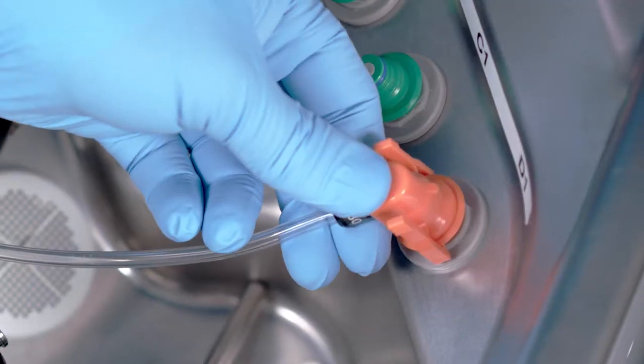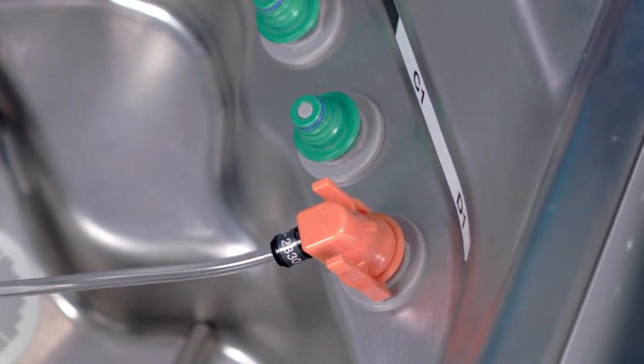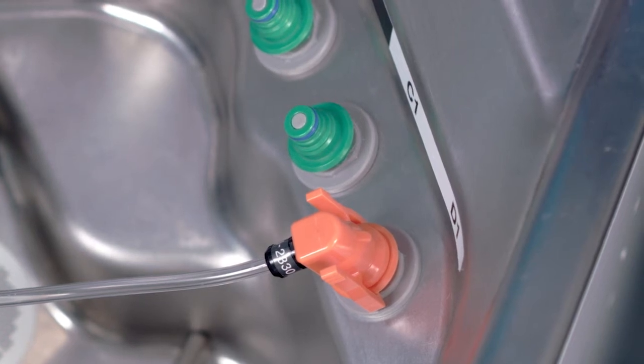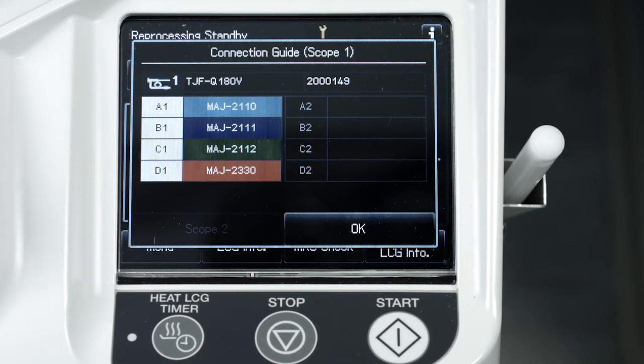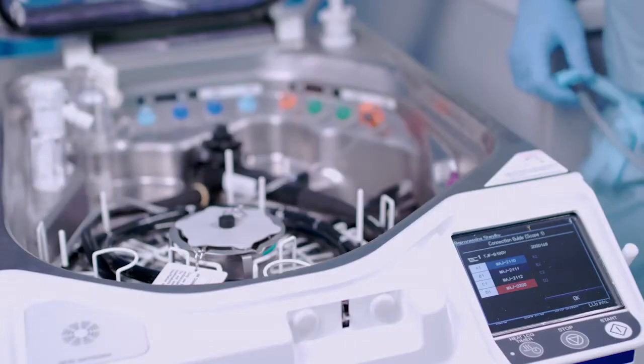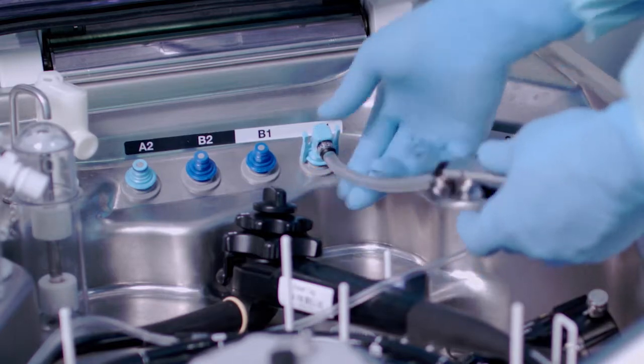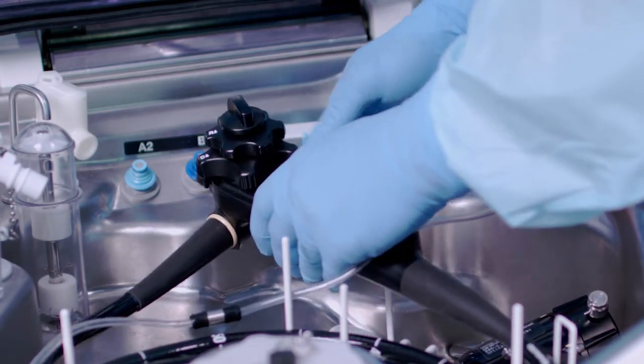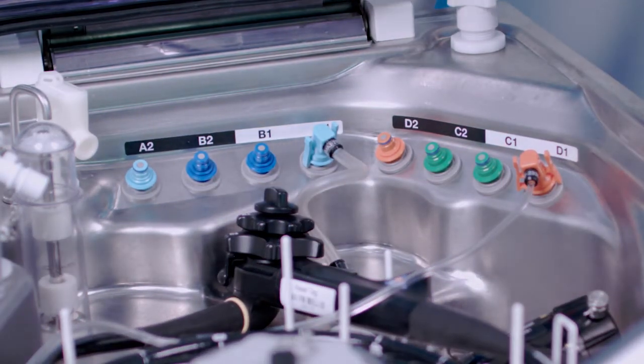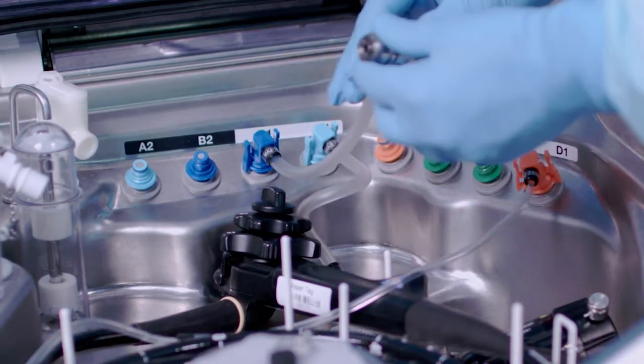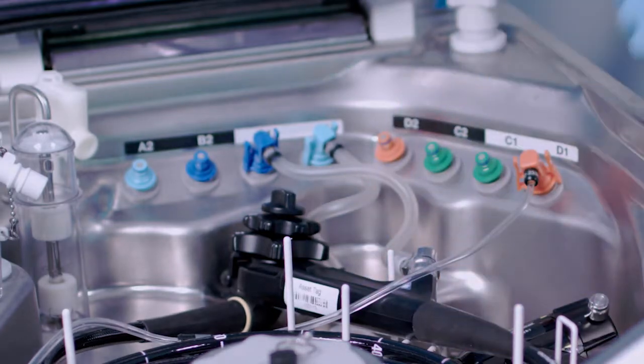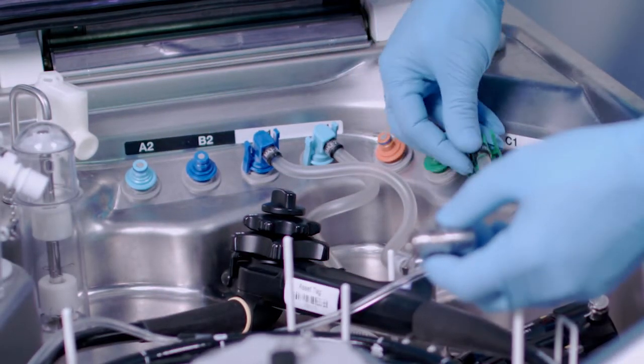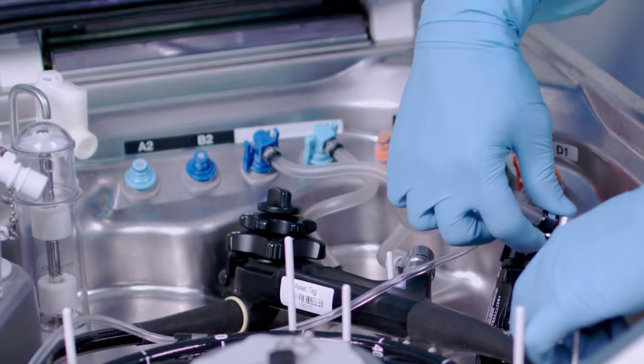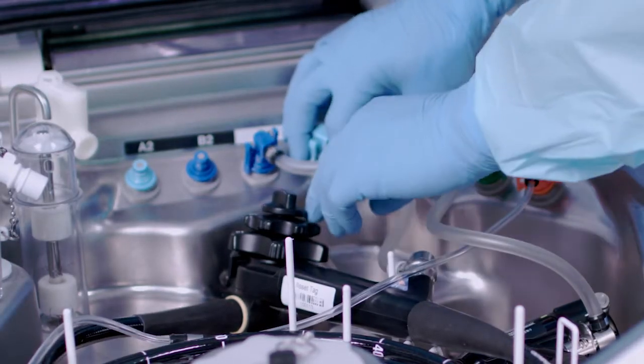Next, snap the reprocessor side connector straight into either of the orange connectors on the reprocessor. Make sure that both sides of the lock levers are securely engaged. The connection guide screen provides the information about the type of connecting tubes required for the endoscope. It will also let the user know the location of the connectors that these connecting tubes are connected to. Select the connecting tube according to the connection guide screen on the display, matching the color of the tube connector to the color and number of the OER-Elite connector. If the connecting tube is connected to the wrong connector, then channel blockage monitoring and channel connectivity monitoring cannot work properly. It is important that none of the connecting tubes are kinked.